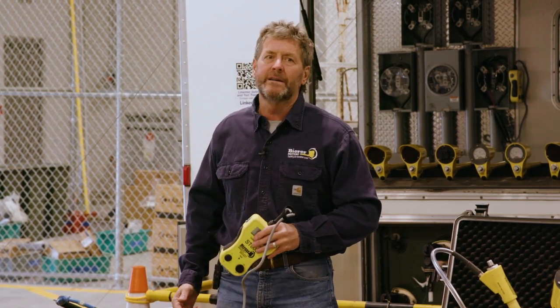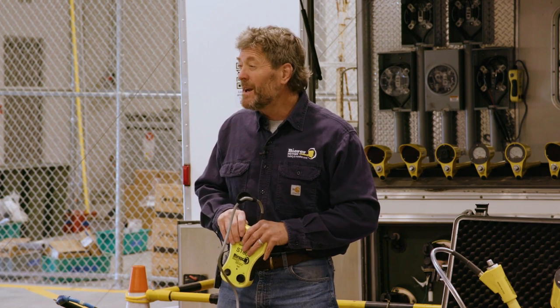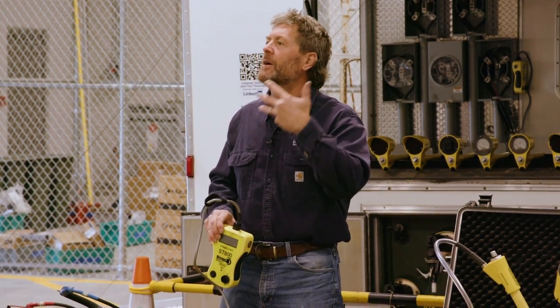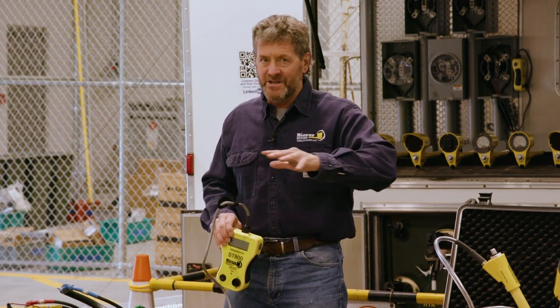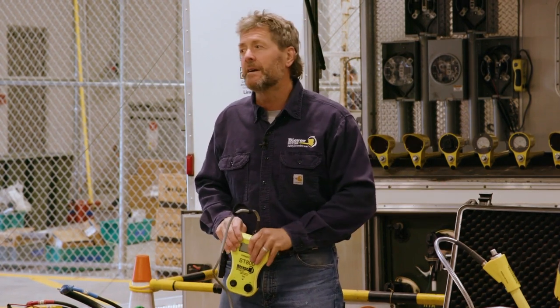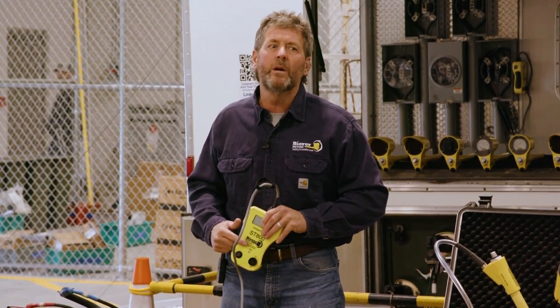You're being proactive. You might have a problem that takes 300 amps to find. So you do it, and you make that repair. Then you go back and retest it, and this time it goes to 800 and holds. So that circuit is now good. And that's not uncommon, because now you're sourcing more load.